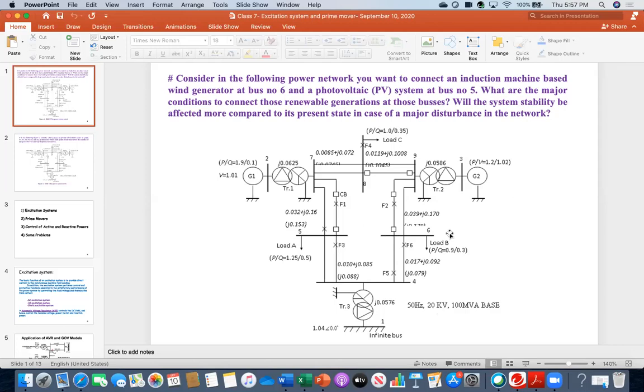If there is a phase difference, then there will be some sort of circulating current flowing from this system to that system, or from IG to this system. Consequently, there will be some sort of heat or power loss in the system. Same thing, if frequency does not match, then there will be circulating current. If voltage does not match, there will be circulating current. And that circulating current will cause some loss in the system, gradual overheating, and might even burn out at some point. So that is the meaning of the first part.